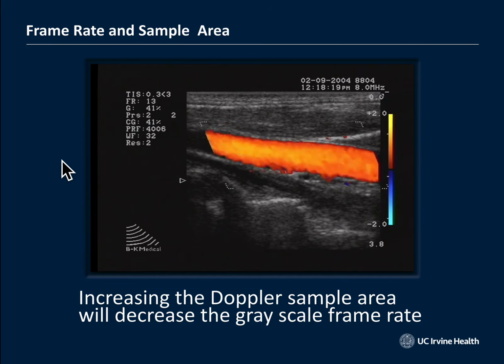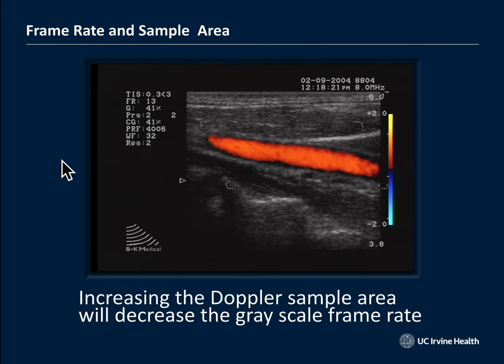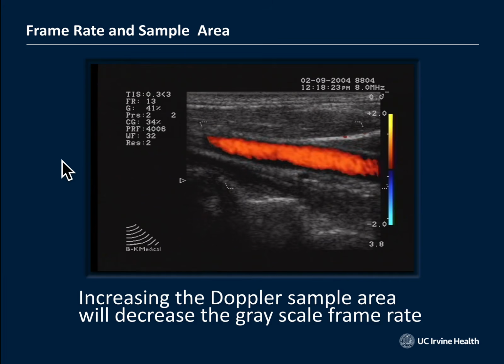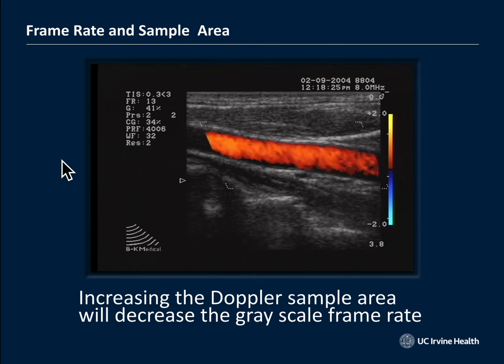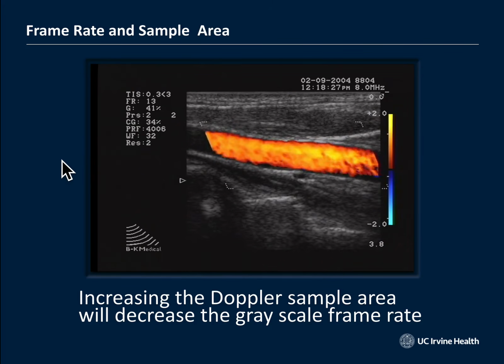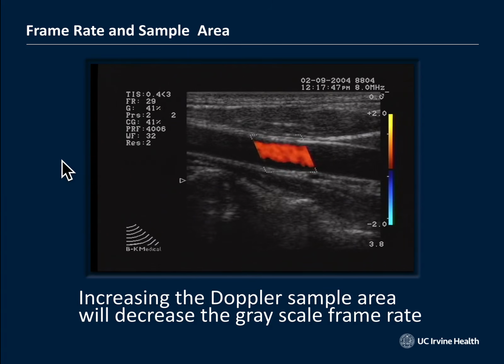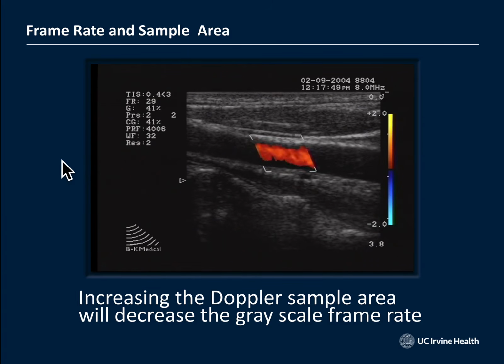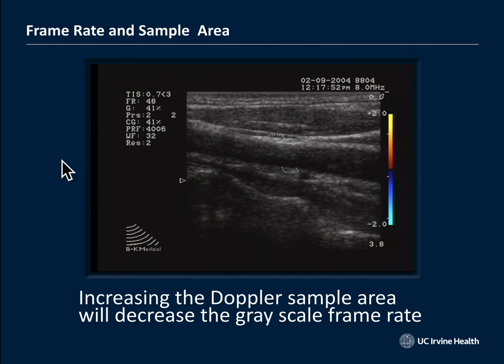As long as I hold my probe really still. But here's what you don't want to do. You don't want to flip on the Doppler or the color and then start dragging the probe around the body looking for a blood vessel, because the probe is going to lag behind what the image shows you, and you're going to get all kinds of flash artifact on the screen.